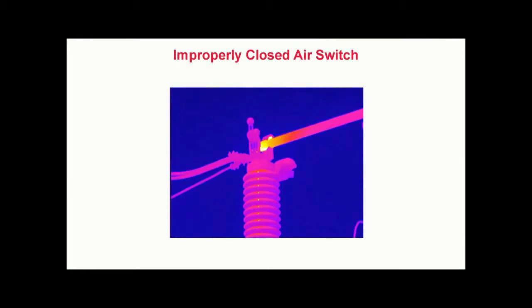Improperly closed air switch. In this thermogram from an outdoor substation, we see localized heating within the jaw of a large air switch. In this image, excess heat is shown in yellow and white.